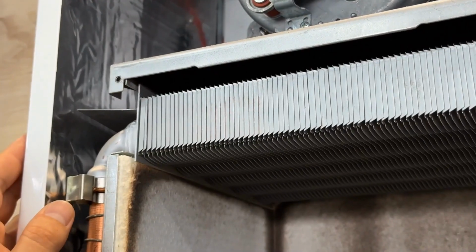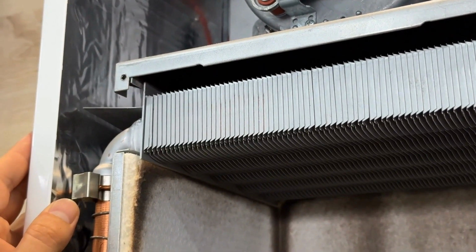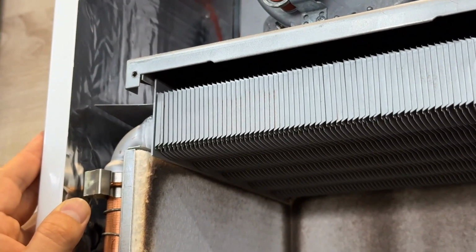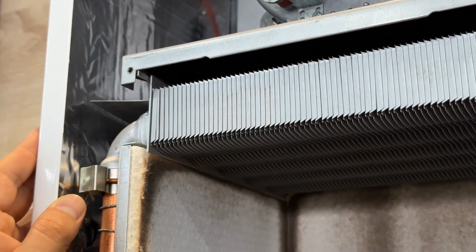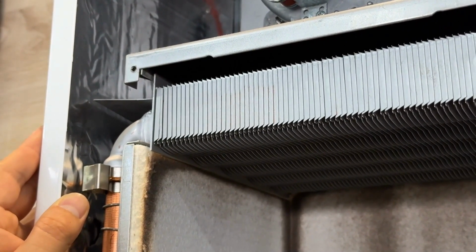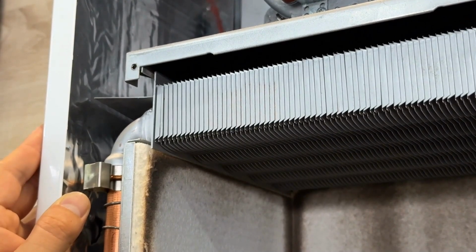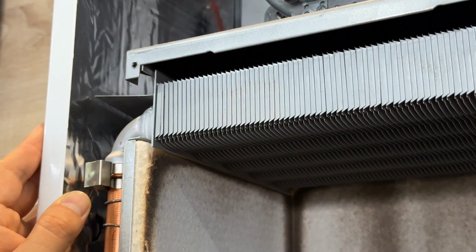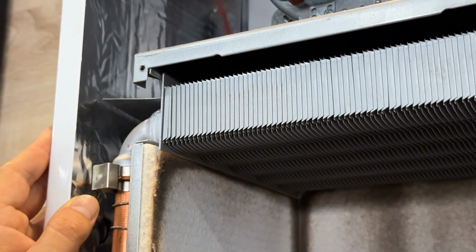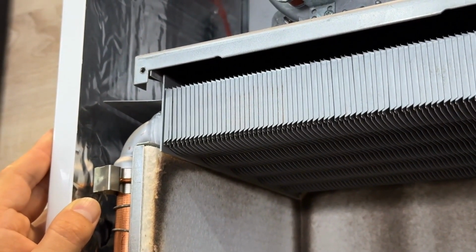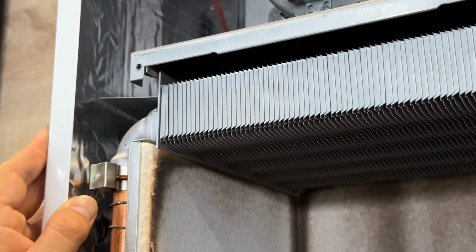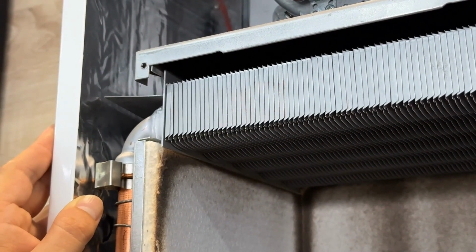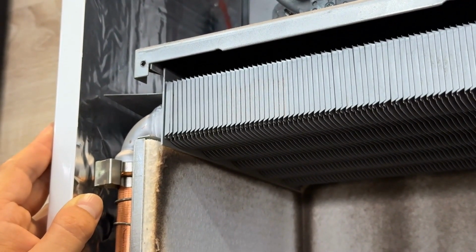The heat exchanger itself is made of pure oxygen-free copper. However, copper actively interacts with condensate. To reduce its impact, a special alloy of aluminum with silicon is used, which covers almost the entire heat exchanger, allowing the minimum temperature of the heat carrier to be reduced to 35 degrees. Nevertheless, such a coating will not 100% protect your heat exchanger. Therefore, temperatures below 50 degrees are recommended only at the very beginning and end of the heating season, for no more than 1.5 months per season.